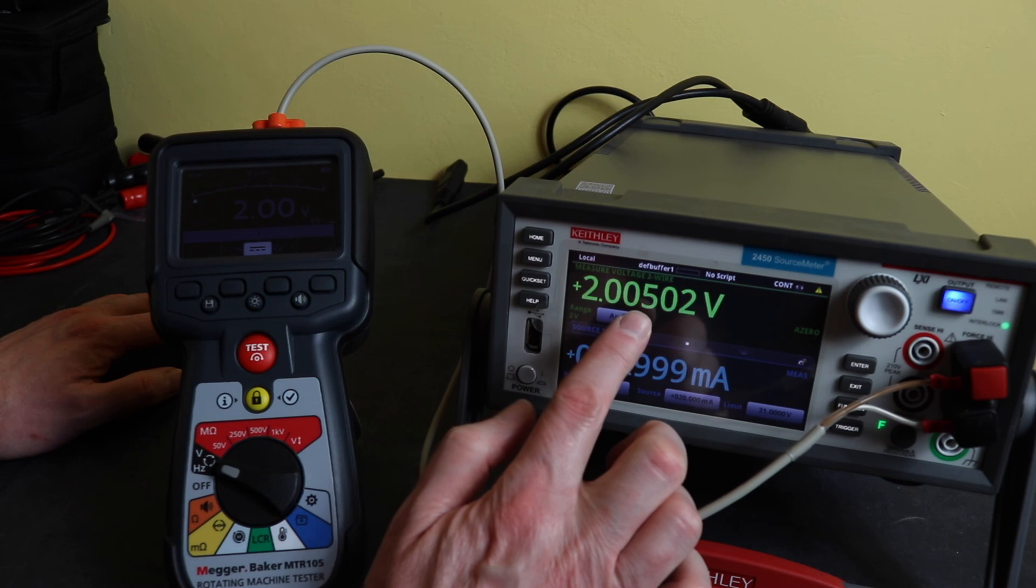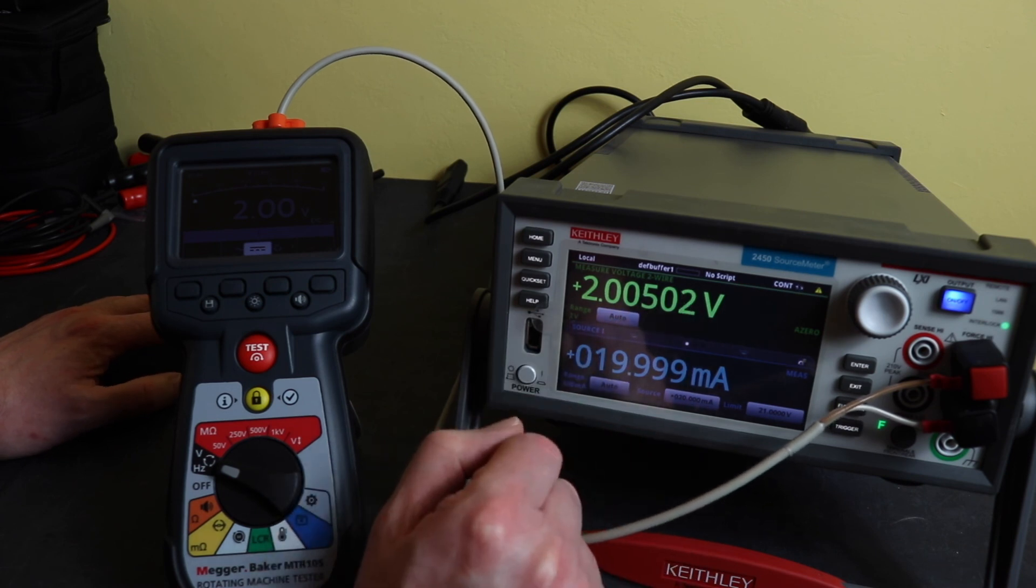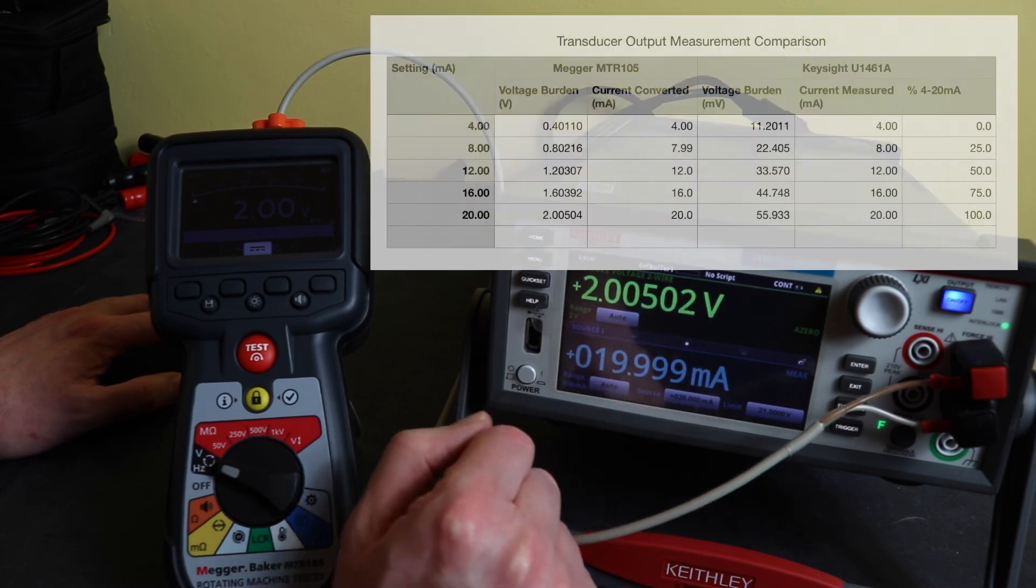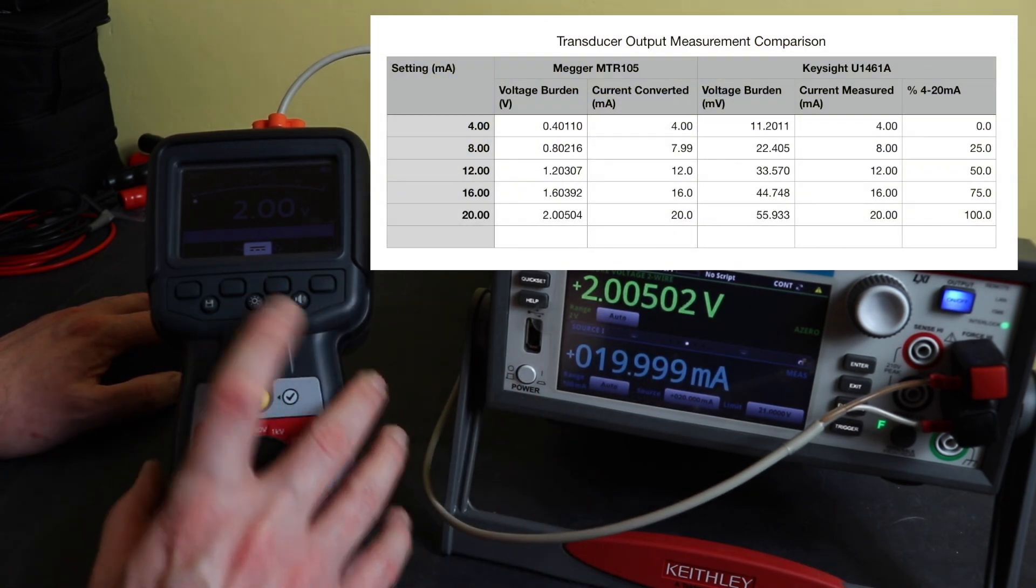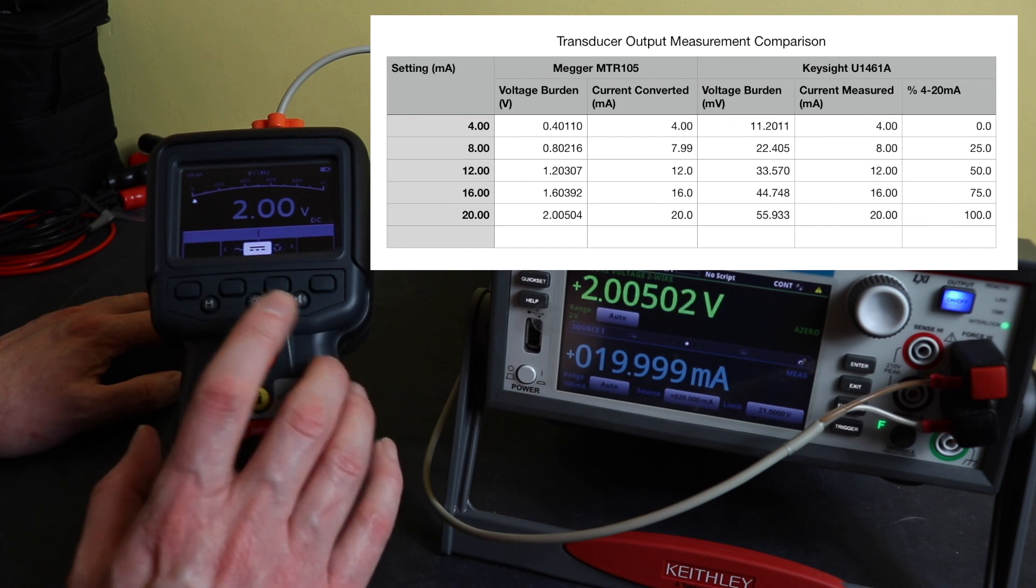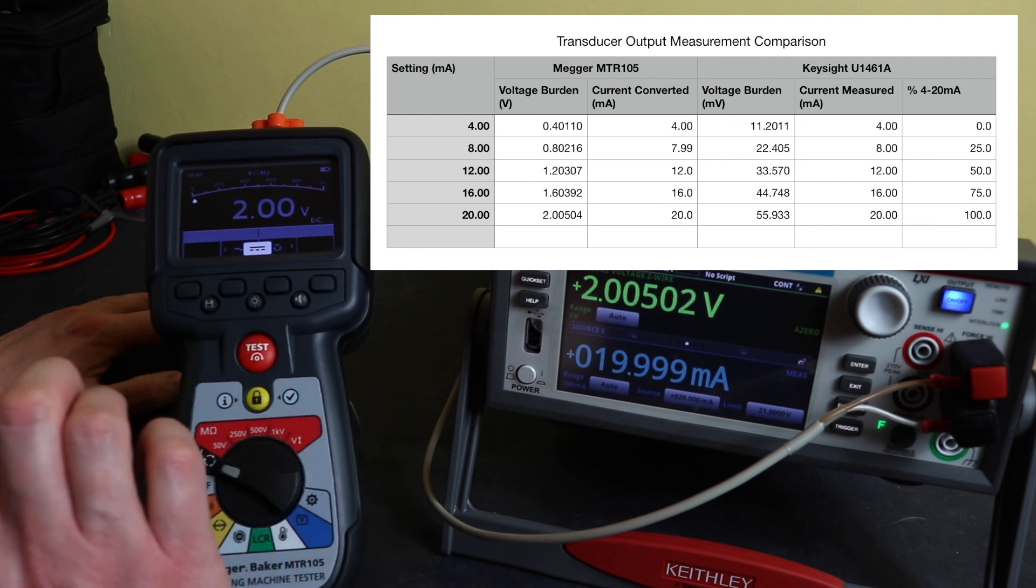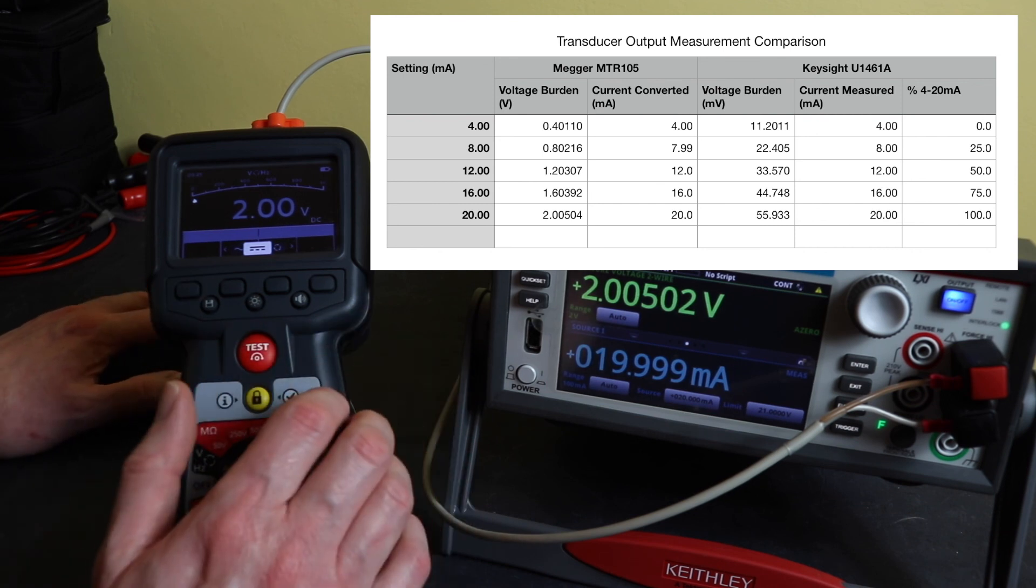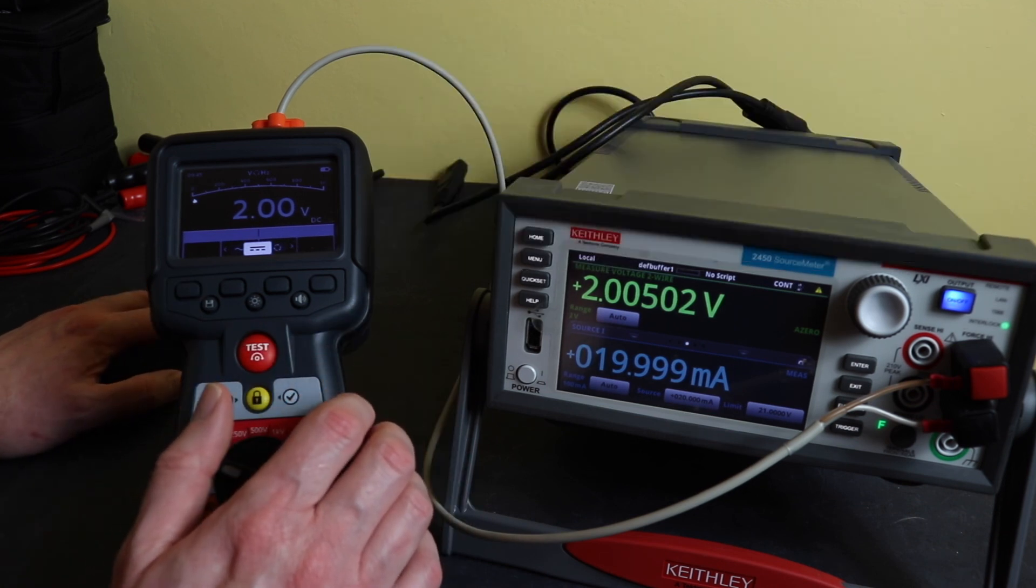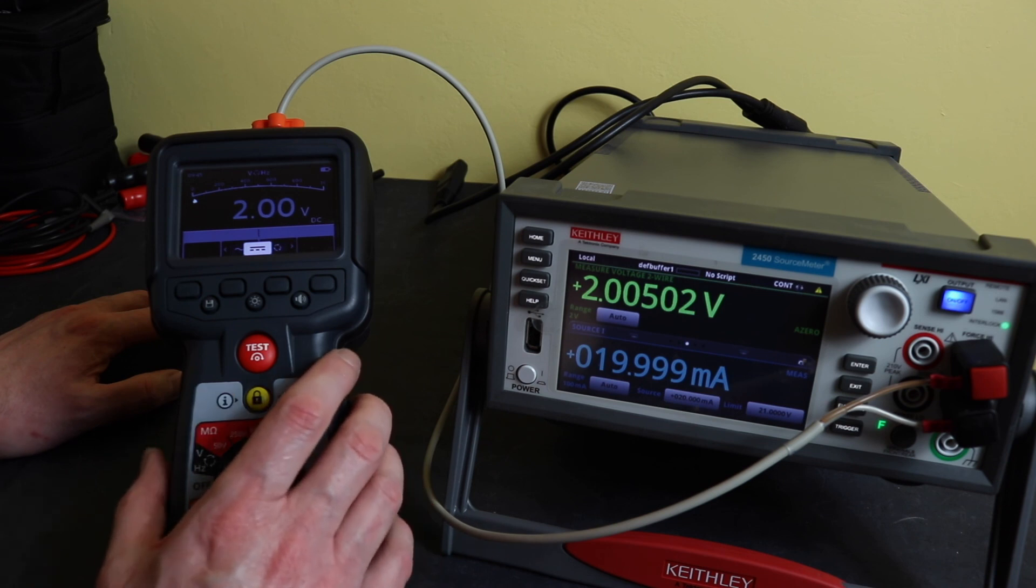Okay what I'll do is I'll stick a table up with the results comparing it to the Keysight. Obviously I do lose a decimal point when I'm doing it with this in comparison to the Keysight instrument, there's a bit more accuracy on there. These transducers will be 0.5 accuracy on them anyway so they're not the most accurate of devices so I kind of feel that testing it in this way would be fairly realistic.